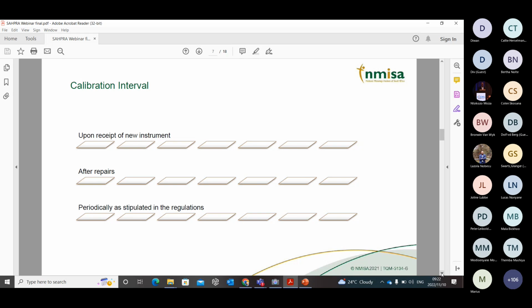One thing that I think I should mention at this stage is we shouldn't confuse calibration with repairs, because we have realized that sometimes one would think that when we do the calibration, we are actually doing some repairs on the instruments, or we are performing some adjustments or something that has to do with the repairs. That is not what we do in the calibration. The instrument needs to be repaired by a certified body, and then after that, taken for calibration.